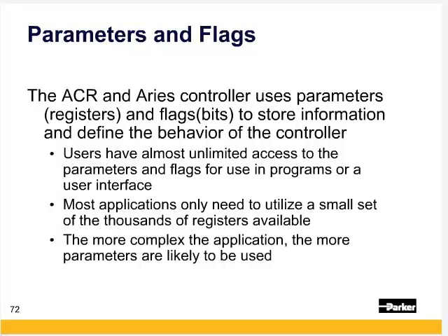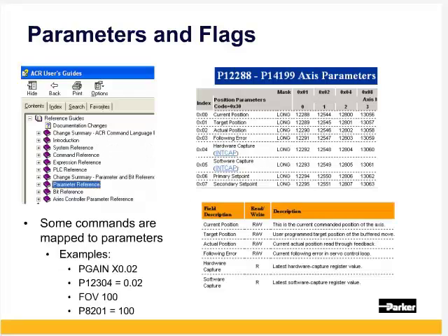The ACR and Aries controller uses parameters, which are registers, and flags, which are bits, to store information and define the behavior of the controller. Users have almost unlimited access to the parameters and flags for use in programs or a user interface. Most applications only need to utilize a small set of the thousands of registers available. The more complex the application, the more parameters are likely to be used. The ACR series are parameter-based controllers, enabling it to be quite powerful with unlimited access.